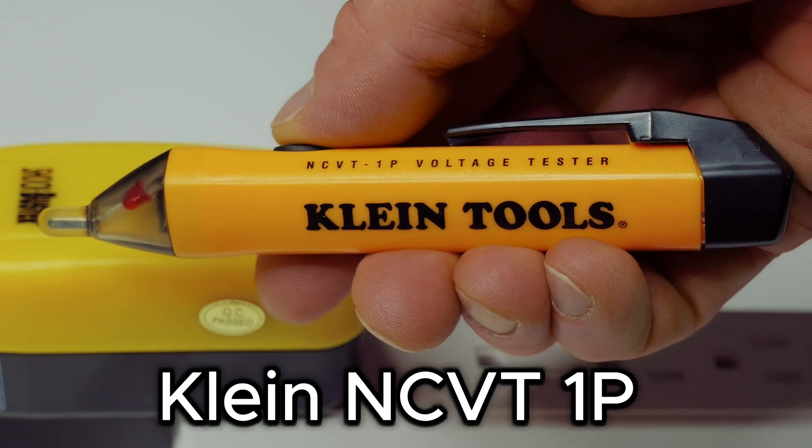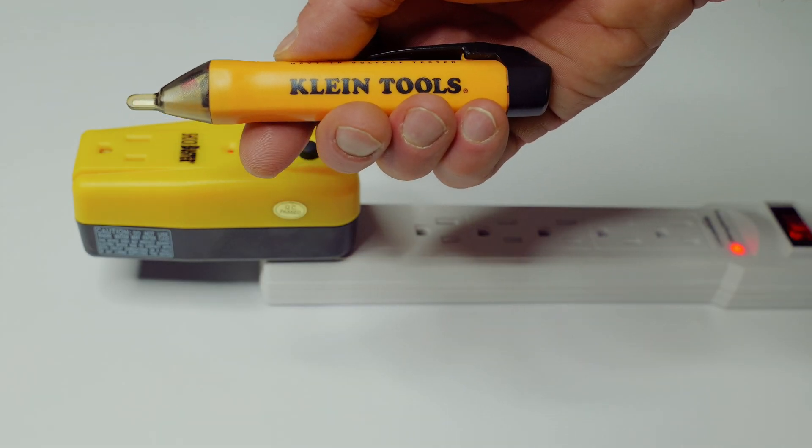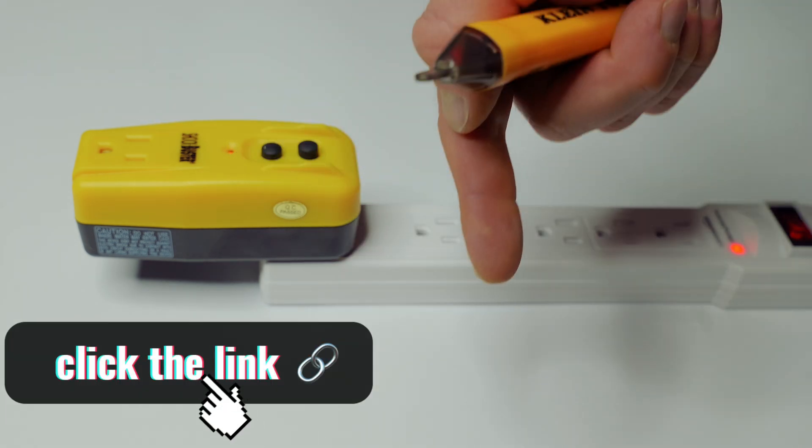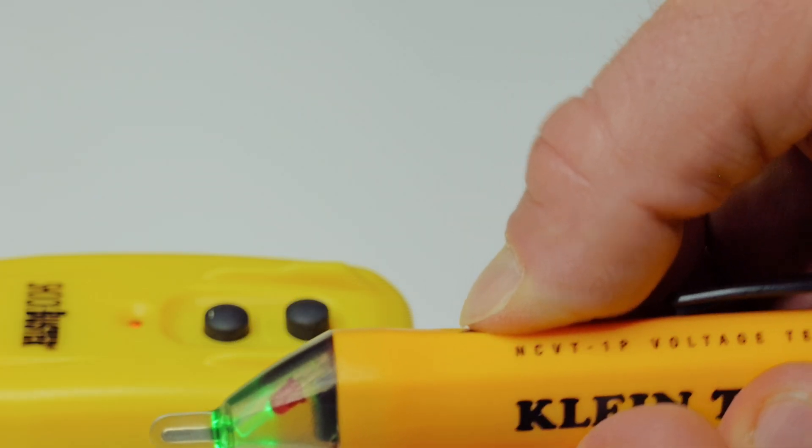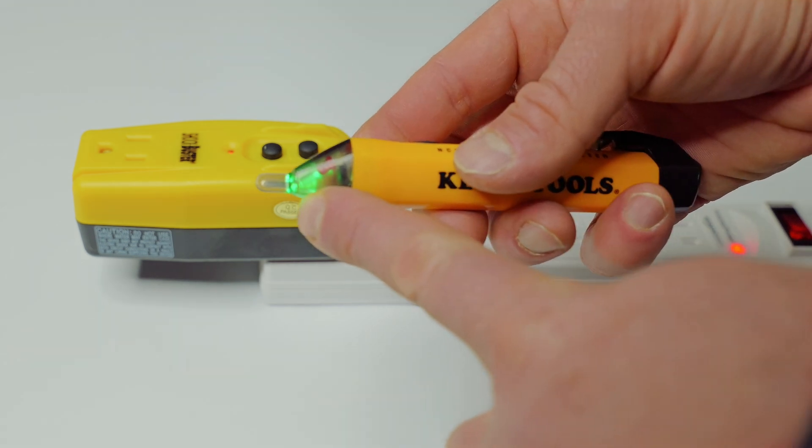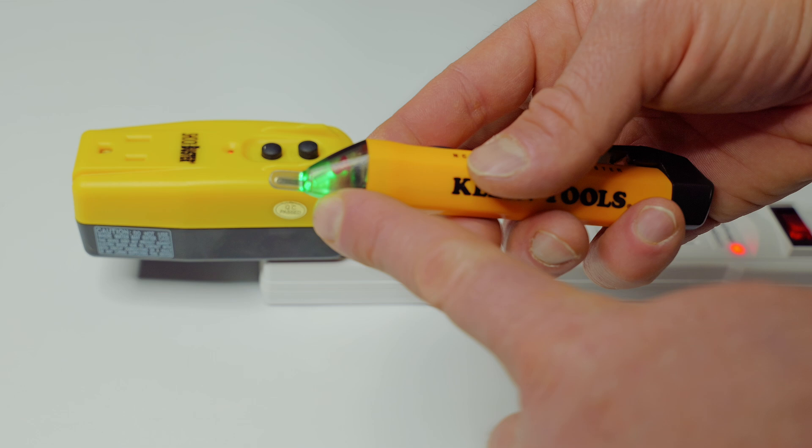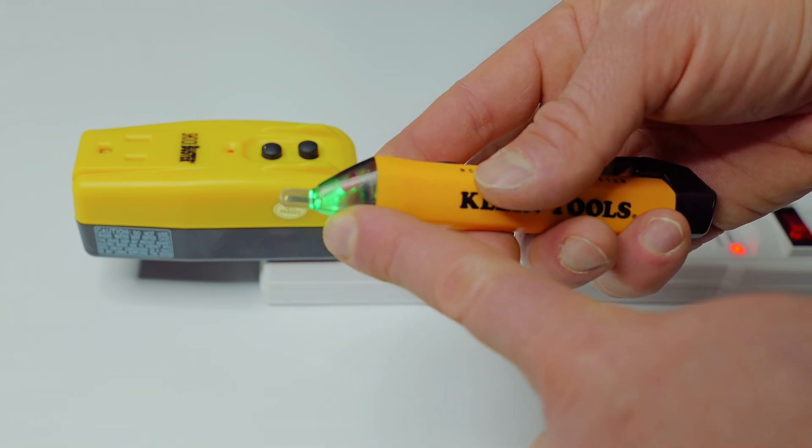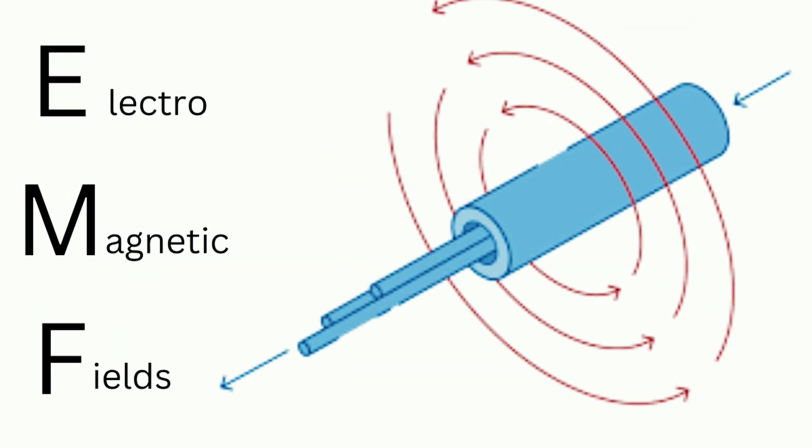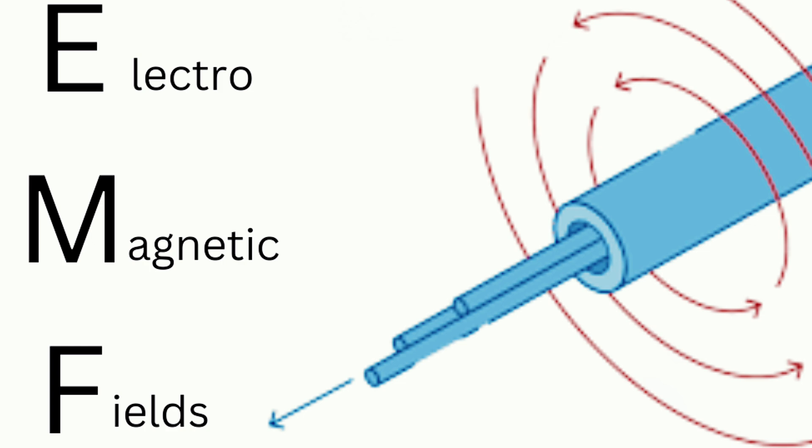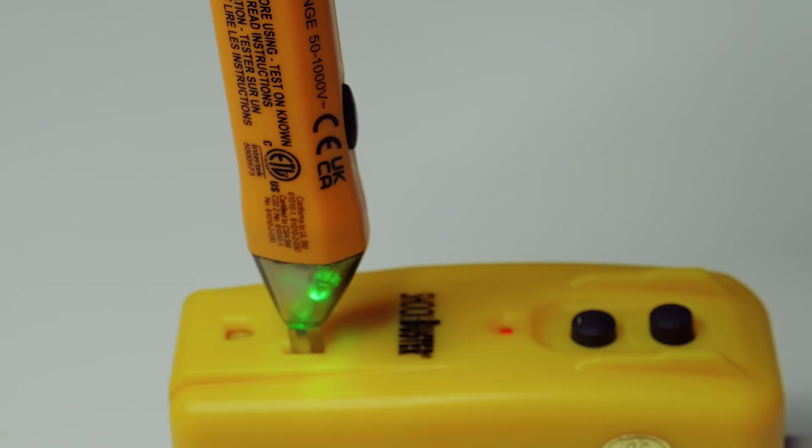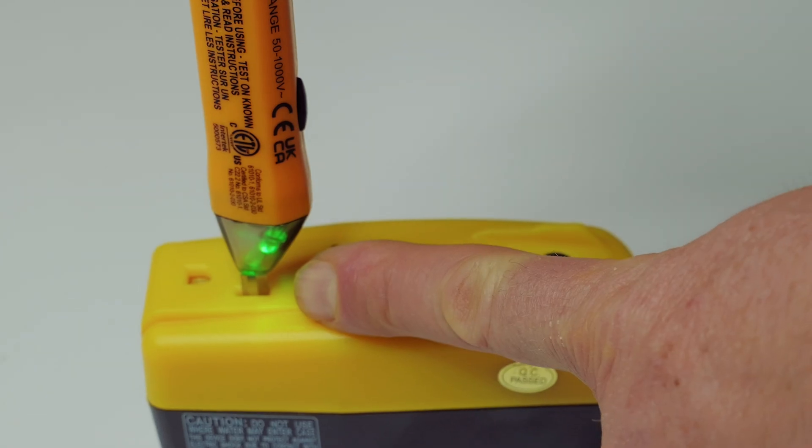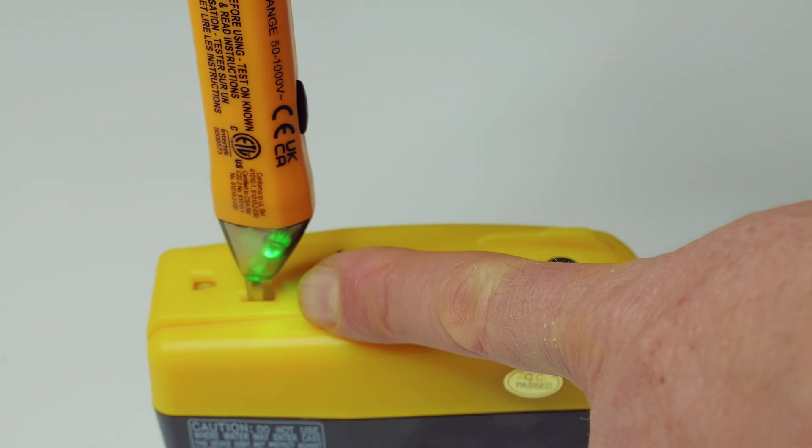Next up is the Klein Tools NCVT 1P. Now this is on Amazon most times for under $25. I'll throw links to all these in the description. So with that said, let's go ahead and test the Klein Tools. Hold down the power button. You can see now that I have a solid green light. That tells me that I'm not near or near enough to any kind of voltage or power source. Now remember these work on EMF power, that's the electromagnetic force that is near an energized circuit. So I'll go ahead and test the neutral side of my socket buster and it's still green. That means that I have no power. So go ahead and insert it into the hot side. As you can see it is still green.